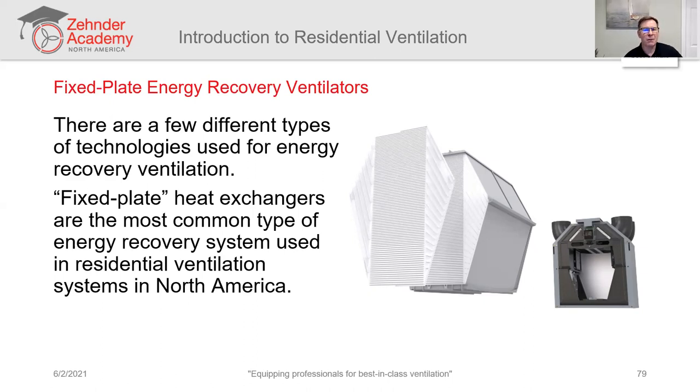The two air streams are kept separate using the geometry and flow management inside the appliance. So the two air streams never actually mix, but they are split up into very fine air streams and passed by each other on opposite sides of these thin plates. And through these thin plates, you have the conduction of heat, and in some cases, also the migration of moisture. But you keep air quality contaminants from one airstream out of the other airstream. So you're able to keep the airstreams from being contaminated, but recover the energy using this device.